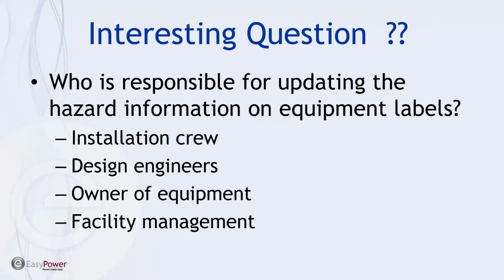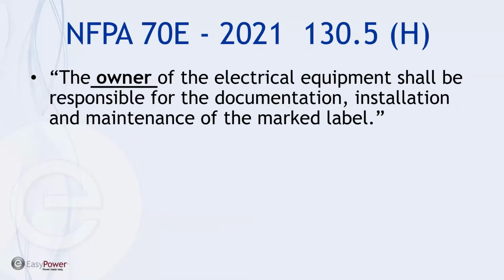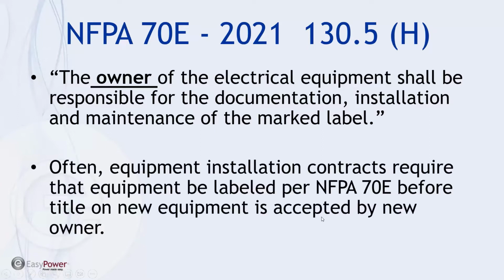Here's an interesting question. Who's responsible for updating information on the equipment labels? This question actually came in from an engineer working in an automation assembly plant. He was getting inputs from several different directions and wanted to know who he should listen to. Well, according to NFPA 70E, the owner of the electrical equipment shall be responsible for the documentation, installation, and maintenance of the marked labels. This brings up another observation: because of this requirement, very frequently equipment installation contracts require that equipment be labeled before taking new ownership of the title per NFPA 70E, because prior to that, the National Electrical Code permitted only a generic arc flash label to be used.